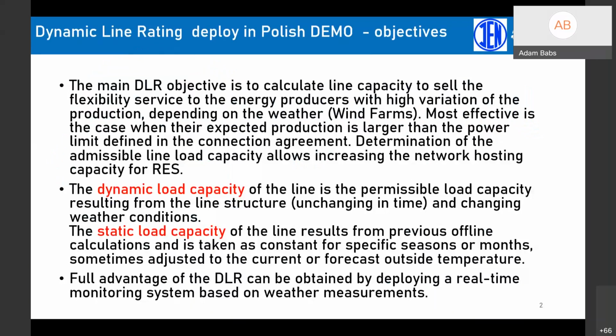It's the permissible load capacity resulting from the line structure, unchanging in time, mostly due to the construction of the line, where it's located, and changing weather conditions, either in real time or, in this case, forecasted weather conditions. This is in contrast to the static load capacity, which is calculated as a constant for a specific season or month, sometimes adjusted to the current or forecasted outside temperature. Then I'll try to explain how it's calculated, and at the end I'll present how DLR is spread out in the Polish power sector.